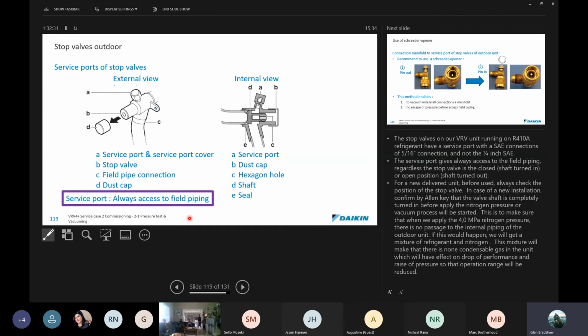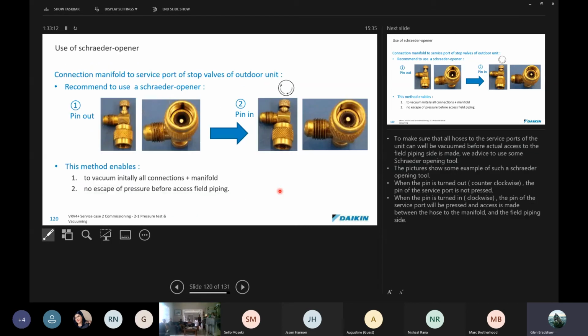Stop valves: always be aware of what the stop valve should be, and you should never open the stop valves until you've completed pressure testing and evacuation. They'll always be turned fully in. You'll also notice that on the new VRV4 Plus units, there's no longer a brass cap on the end, there's a plastic cap. These valves seat on both a taper and an O-ring, so they deem that they don't need the brass cap anymore, but you are required to put the plastic cap back on. This just prevents dust and moisture from getting in there and causing corrosion and eventual failure of the seals. So just keep that in mind.